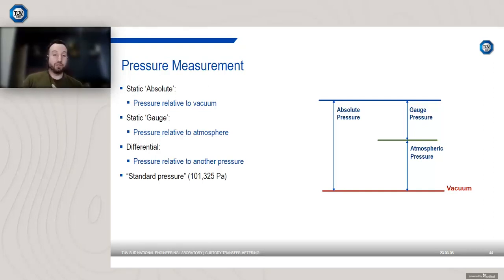They're obviously important for safety, but when it comes to dealing with pressure measurement, it's important to be clear on the terminology. You'll hear absolute static pressure and you'll hear gauge static pressure. What is the difference between them? Absolute pressure is pressure measured relative to a vacuum. Gauge pressure is pressure measured relative to the atmosphere. It's important to know whenever a pressure is stated whether it is the absolute or the gauge pressure, because these terms can be confused.